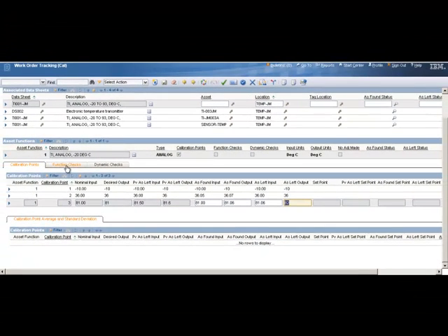Normally, sometimes you have function checks, dynamic checks. Sometimes you may have a second calibration function for discrete checks. And discrete checks are basically switches and alarms. So if I'm reading a temperature indicator or a pressure indicator, maybe at 100 psi it gives me a warning alarm, and maybe at 125 I get a high pressure alarm. That's an indication of a discrete component. And I may have to calibrate that by increasing my input signal to the right point and making sure that set point goes off. That would be discrete. And when you set your data sheet up, you'll set them up as function 2 might be discrete checks. And you have 1 or 2, however many calibration points there are.